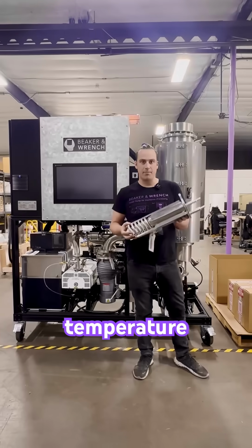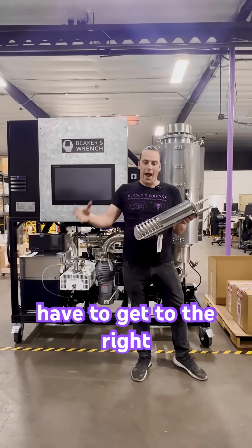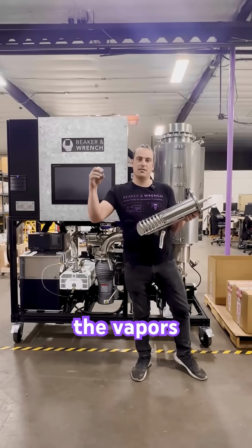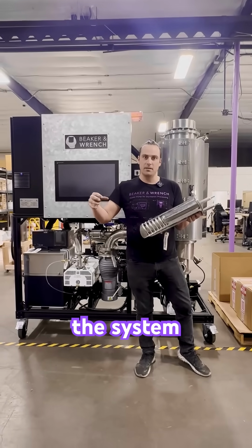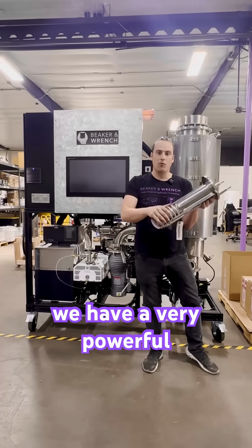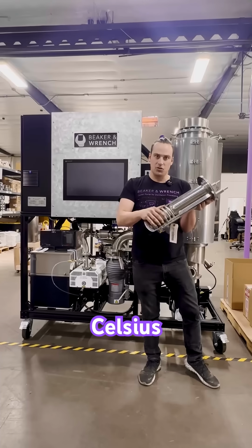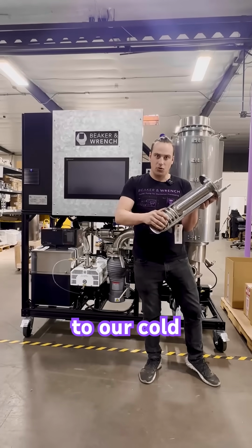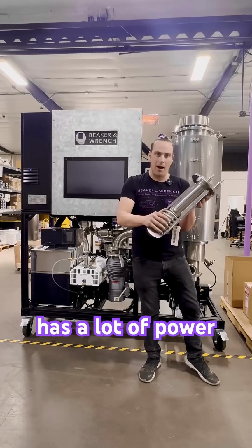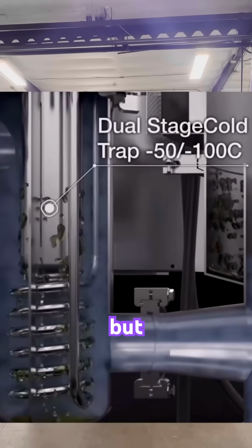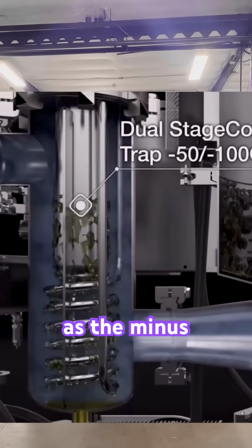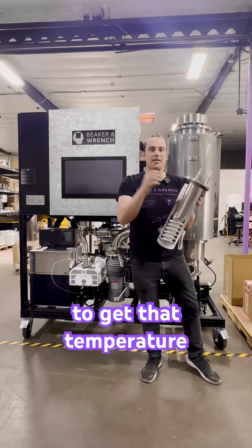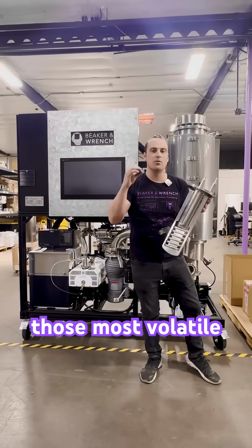And the last one is temperature. Because you have to get to the right temperature to condense the vapors that you want in the system, that's why we have a very powerful minus 55 Celsius chiller as a pre-stage to our cold trap, which has a lot of power, overcoming the second limitation. But it's just not as cold as the minus 100 Celsius.